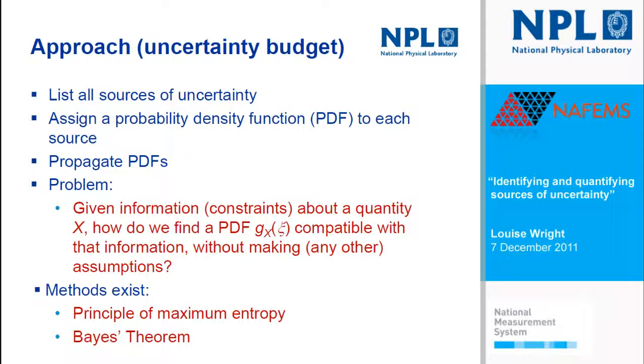The way we approach uncertainty evaluation within the measurement community is to create something called an uncertainty budget. This gives you a structure to know that you've taken everything into account. It consists of a list of all the sources of uncertainty and assigns a probability density function to each of those sources, and then the budget allows you to propagate and combine the PDFs. The question you have to ask yourself is: given a set of information, how do I know what PDF to assign?